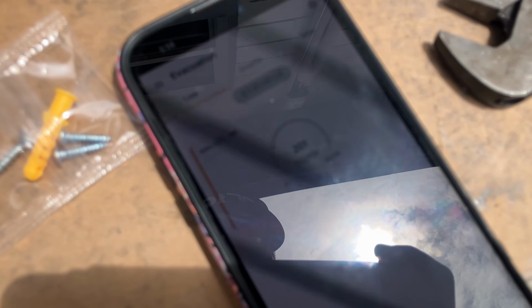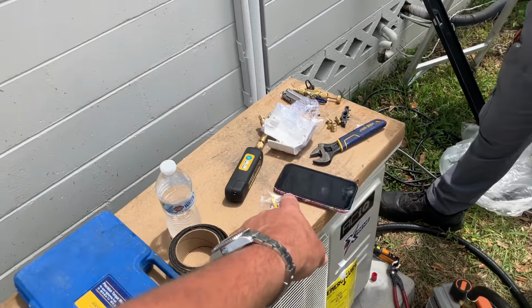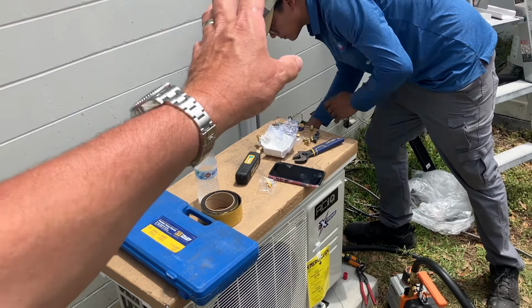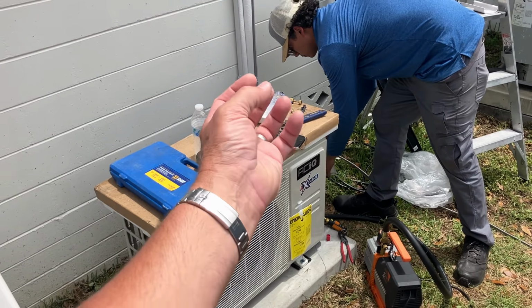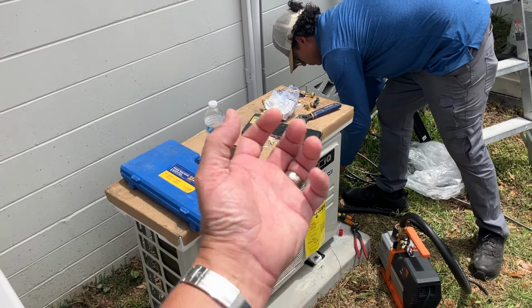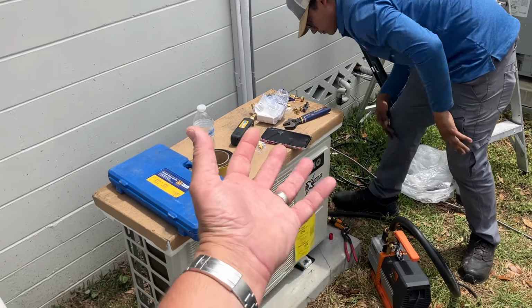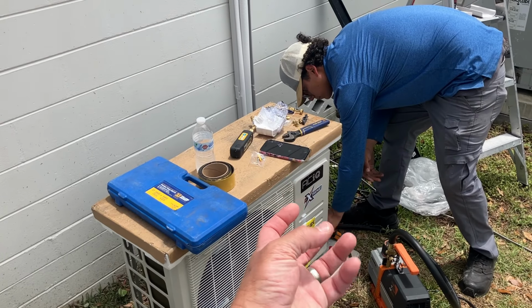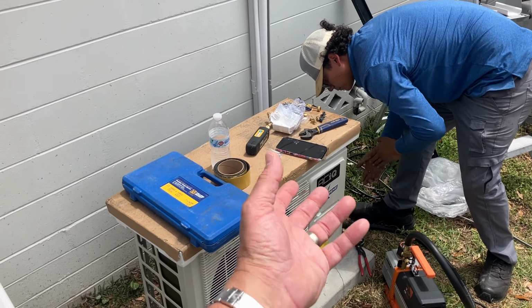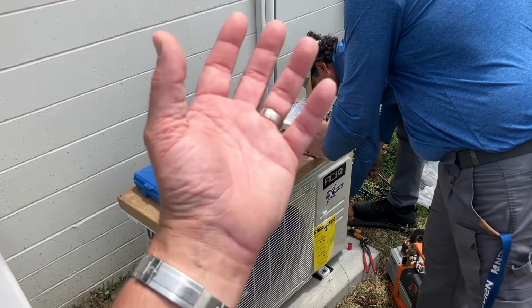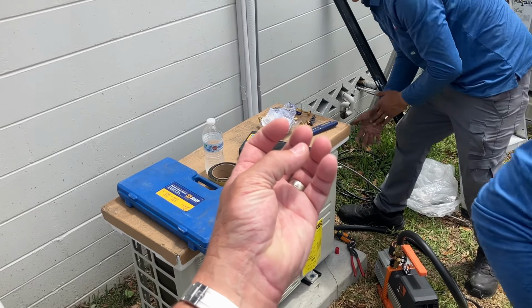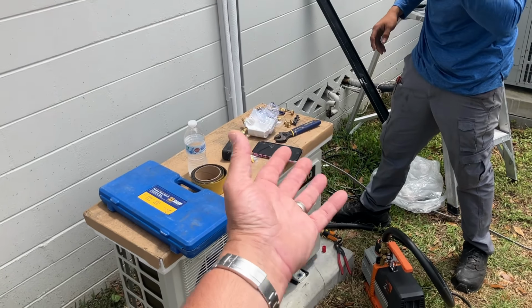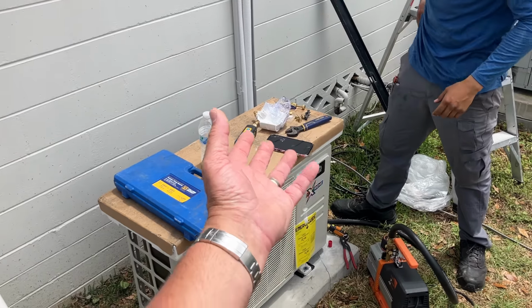All right, folks, we are at 200. I don't know if you can see that on your screen. 199, 198, 201, 199, 198. Now remember, folks, this number is going to change. It could jump up a little bit, it could jump back down, because as we're in that negative atmosphere, we're in a vacuum. So any moisture, which is water, is boiling off, and that's going to expand drastically. And that's going to throw off your inches of water column, but you're not in inches of water column, you're in negative pressure, so we measure in microns.